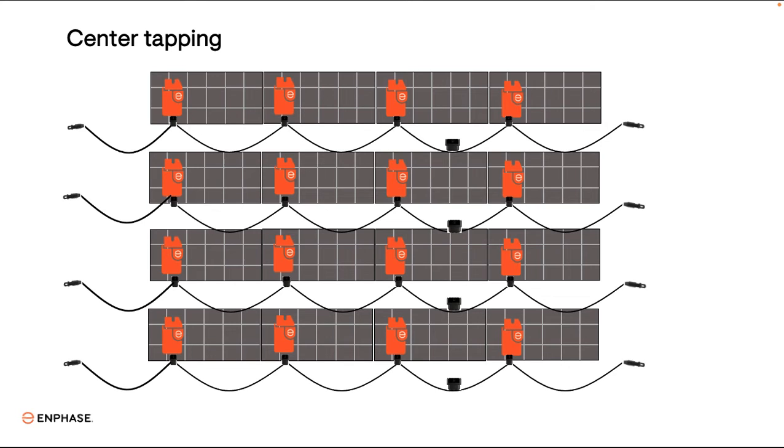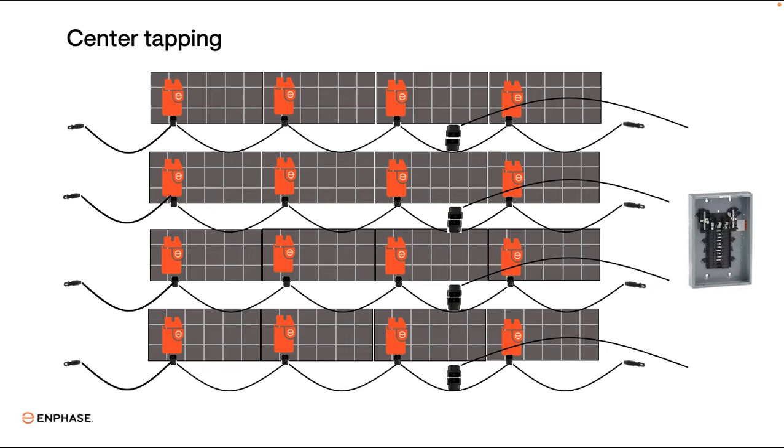All of our cabling options include a center tap connector intended to mitigate against problems that may arise due to voltage rise. You'll find that there is a center tap connector after every 6 drops on the QD cable. You should wire those center tap connectors to our center tap adapter cable and run that to your subpanel as a home run. When you wire in a home run at either end of the QD cable, voltage rise becomes quite high. But by wiring into the middle, your voltage rise percentages will stay within range as long as the rest of your system is sized appropriately.